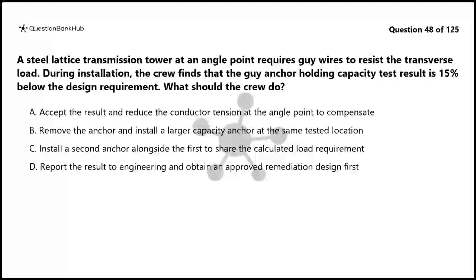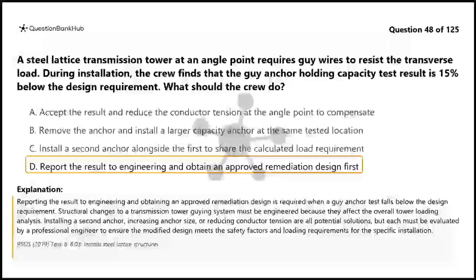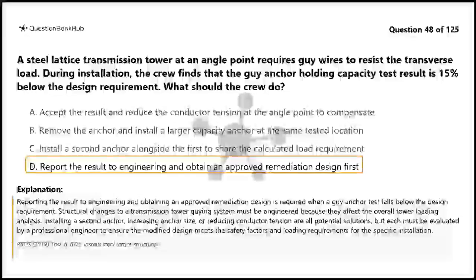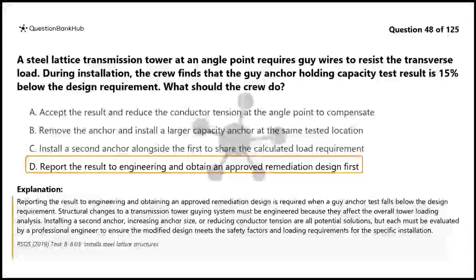The correct answer is D. Reporting the result to engineering and obtaining an approved remediation design is required when a guy anchor test falls below the design requirement. Structural changes to a transmission tower guying system must be engineered because they affect the overall tower loading analysis. Installing a second anchor, increasing anchor size, or reducing conductor tension are all potential solutions, but each must be evaluated by a professional engineer to ensure the modified design meets the safety factors and loading requirements for the specific installation.